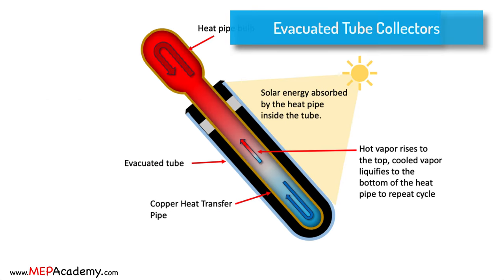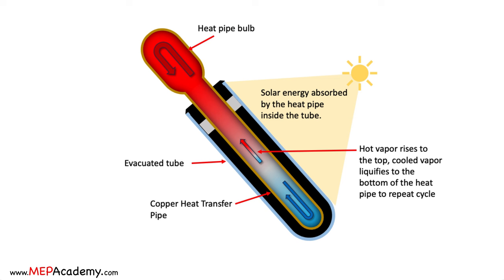Evacuated tube collectors consist of rows of glass tubes with an outer and inner tube. The air is evacuated from the space between the tubes to create a vacuum, reducing heat loss through conduction and convection. Like flat plate collectors, sunlight passes through the outer glass tube and strikes an absorber within the inner tube. The absorber transfers the heat to a fluid circulating within the tube. Evacuated tube collectors are more efficient than flat plate collectors, especially in colder climates. The vacuum insulation minimizes heat loss, allowing them to capture solar energy even on cloudy days.